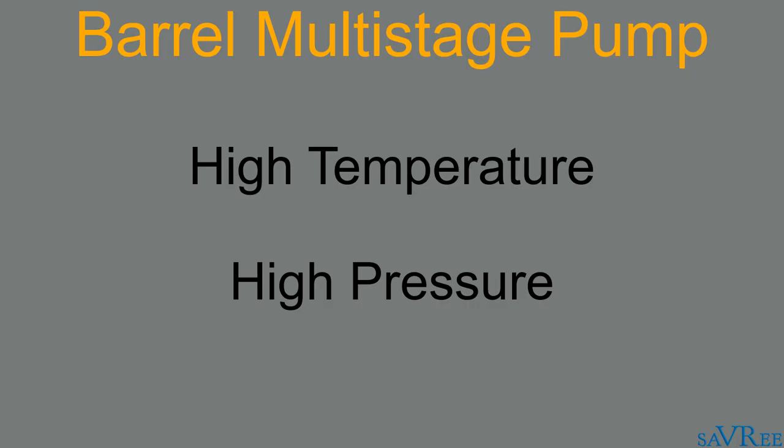Ring section multistage pumps are also used for high temperature and high pressure applications, although there are some differences between the two designs. The barrel type pump allows for the internals of the pump to be removed without disconnecting the outer casing and much of the associated piping.